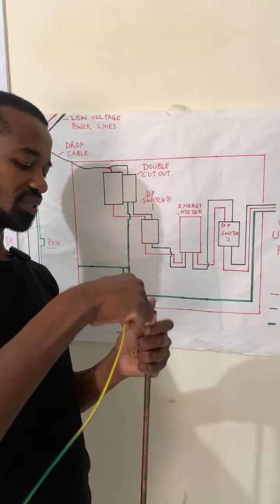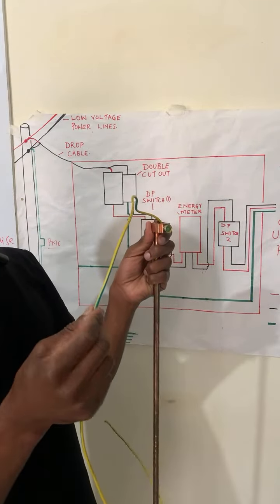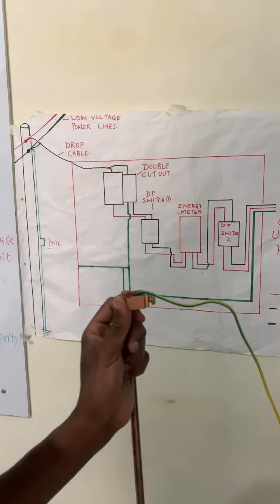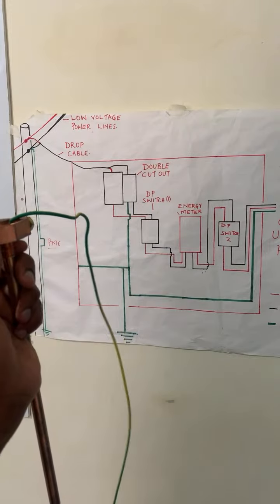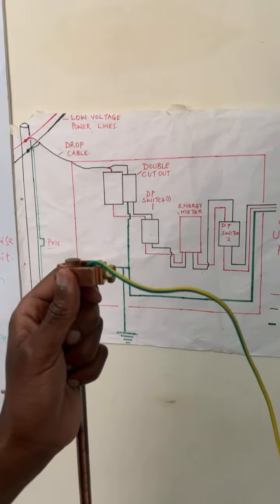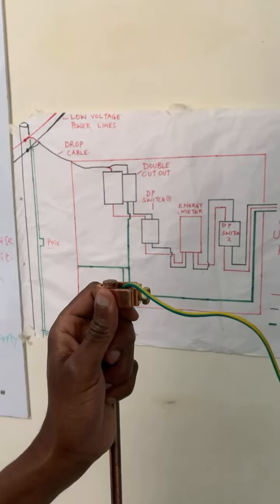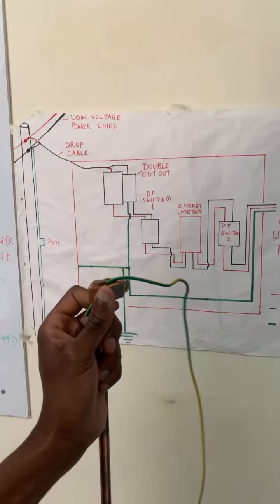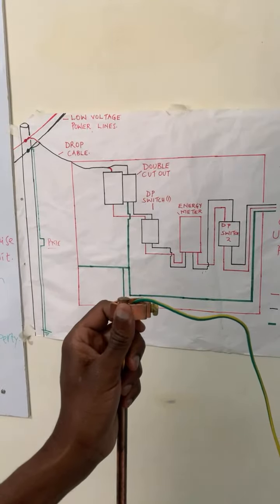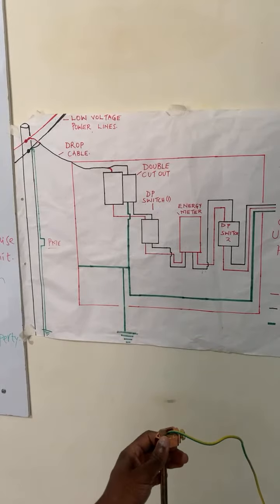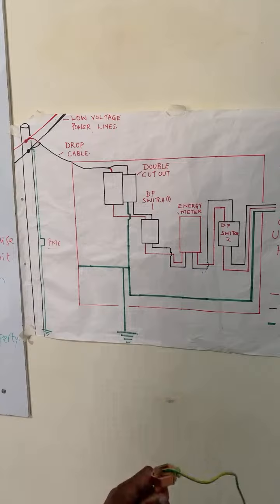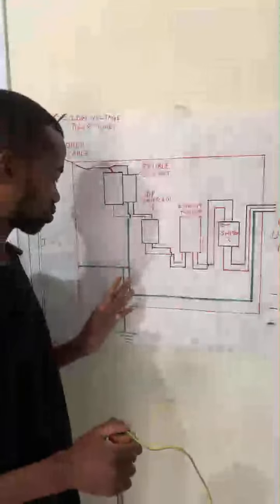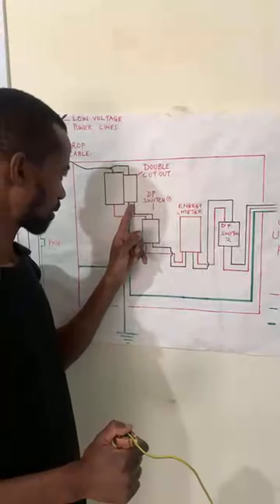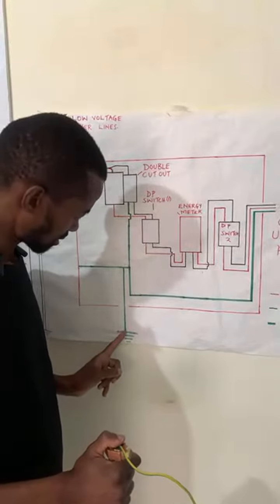So whenever someone sees this cable, they will know that this is a green with a yellow stripe, or is it yellow with green stripes? Top boss, what do we refer to that earth cable? And let me just know from the comment section, what is the ideal size of the cable or the wire that is actually earthing, connecting the earth rod from the meter box all the way to the ground? What is the ideal cable size from this point? In fact, that cable size should be consistent from the point where you are bonding at this point, going all the way to the earth rod, which is this one.